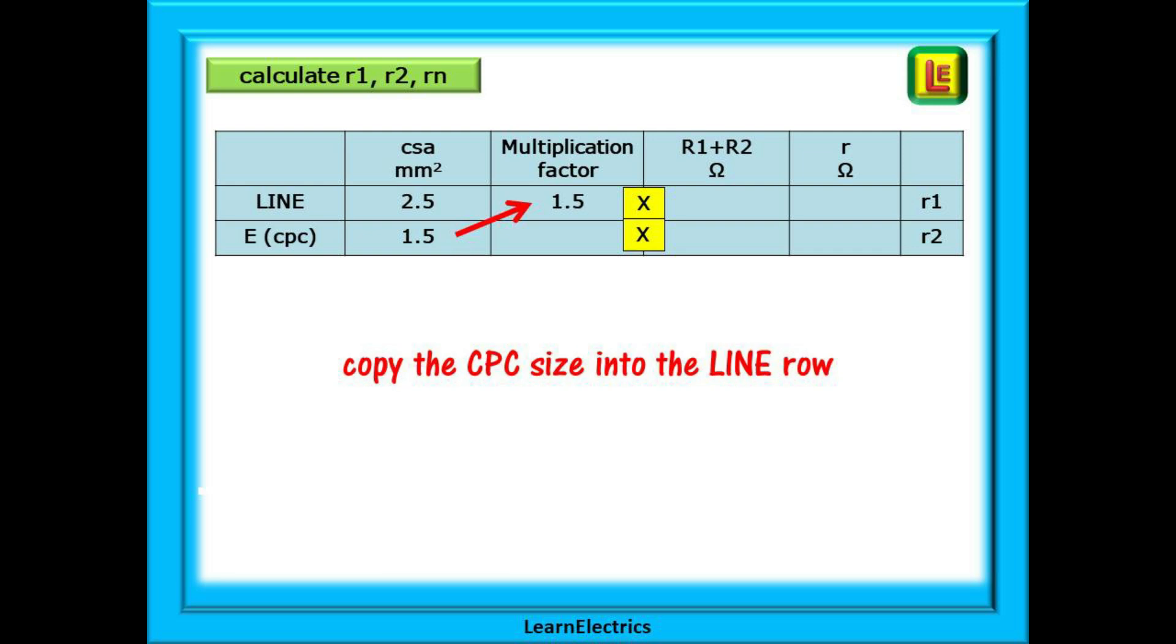Put the 1.5 for the CPC into the top row for the multiplication factor, and then the 2.5 for the line into the box on the CPC row. Enter big R1 plus big R2 that we just calculated into the column, and notice that there is a multiplication sign in yellow boxes between the two columns.